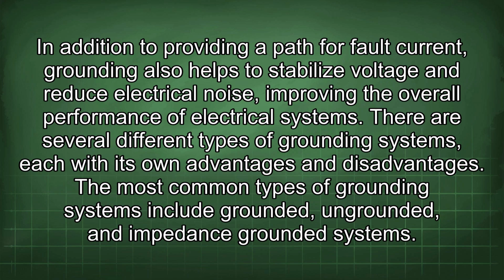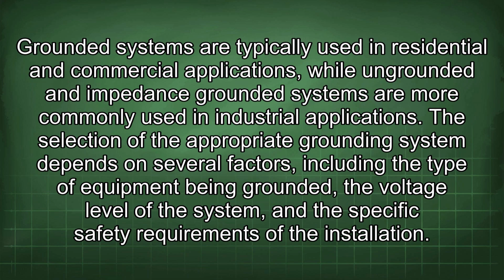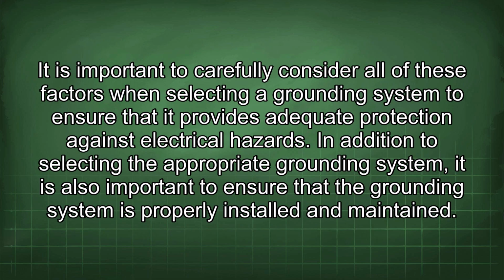There are several different types of grounding systems, each with its own advantages and disadvantages. The most common types of grounding systems include grounded, ungrounded, and impedance-grounded systems. Grounded systems are typically used in residential and commercial applications, while ungrounded and impedance-grounded systems are more commonly used in industrial applications. The selection of the appropriate grounding system depends on several factors, including the type of equipment being grounded, the voltage level of the system, and the specific safety requirements of the installation. It is important to carefully consider all of these factors when selecting a grounding system to ensure that it provides adequate protection against electrical hazards.